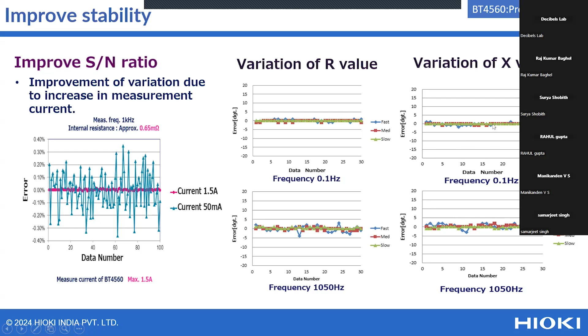We also tested the variation of resistance at different speeds. In the BT4560, there are three modes available: fast, medium, and slow response speed. We can see the result is mostly stable, not much fluctuating at 0.1 Hz. The same data we can also observe at 1 kilohertz approximately, and the result is stable. Similarly, we checked the variation of reactance with respect to speed, and in this case also the results are stable.